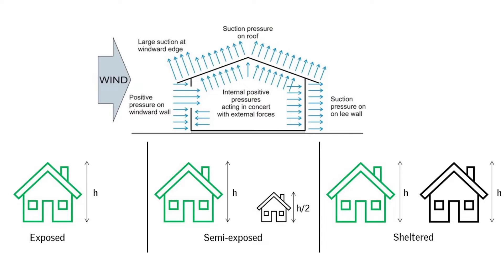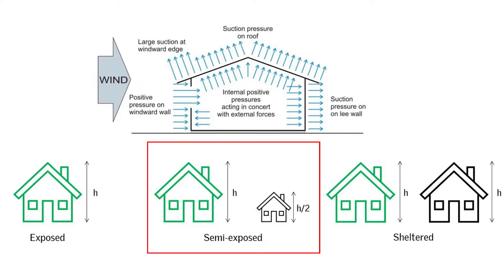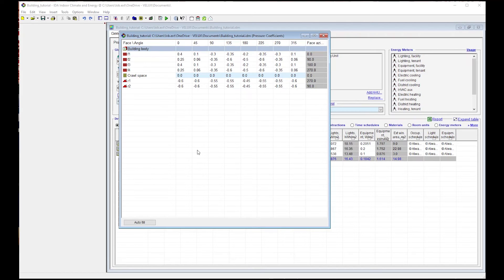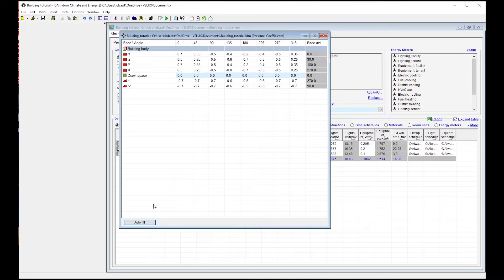There are three different exposure classes: exposed, semi-exposed, and sheltered. Exposed is when the building is not surrounded by any relevant obstructions. Semi-exposed is when the building is surrounded by obstructions with a height close to half the height of the building. Sheltered is when the building is surrounded by obstructions with at least the same height as the building. By using the Autofill button in the software, you can choose between these three exposure classes according to the building's location, and IDA ICE will determine the pressure coefficients automatically – no need to change them manually. For example, choosing the exposed situation gives higher pressure coefficient values, leading to higher wind-driven airflows.